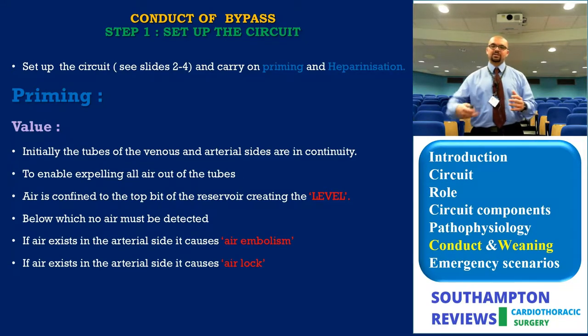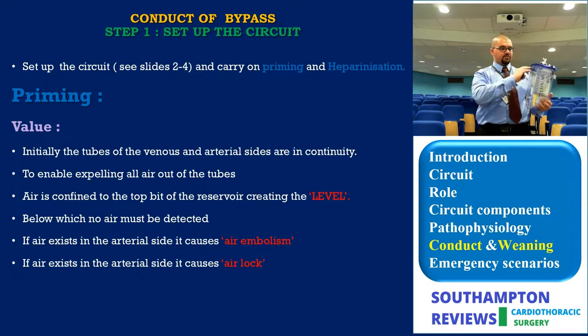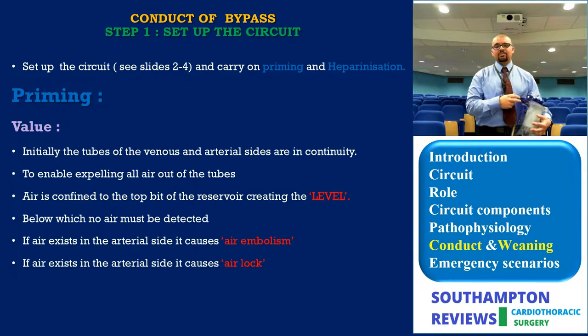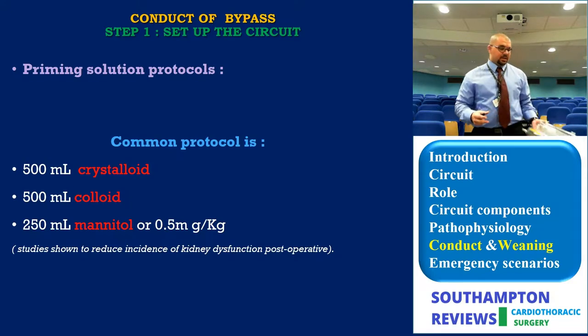Initially you fill the circuit through the ports of the container, run it, and expel air out via a sideway, condensing all air at the top of the reservoir. Around one and a half to two liters is sufficient to fill the whole circuit, with air confined to the top of the container. The level below which no air must be present is critical — air on the arterial side causes air embolism; air on the venous side causes air lock.